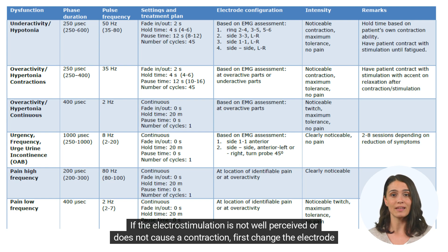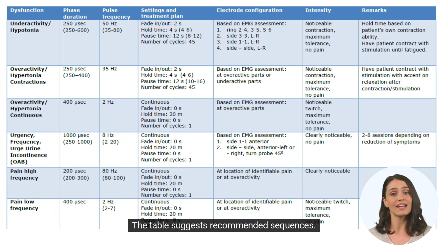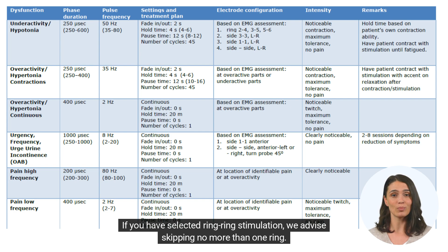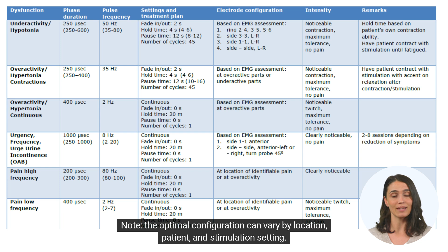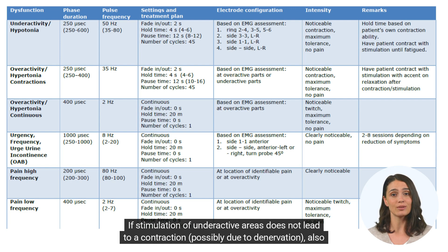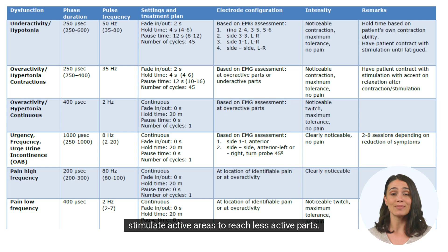If the electrostimulation is not well perceived or does not cause a contraction, first change the electrode configuration. The table suggests recommended sequences. If you have selected ring-ring stimulation, we advise skipping no more than one ring. Note, the optimal configuration can vary by location, patient, and stimulation setting. If stimulation of underactive areas does not lead to a contraction, possibly due to denervation, also stimulate active areas to reach less active parts. Adjusting phase duration and frequency.